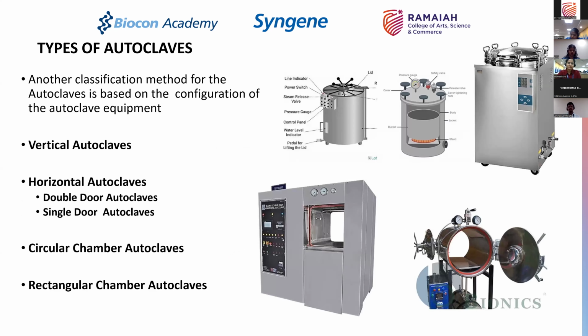Okay. Now, the third type of classification is also based on the geometry or the configuration of it. Now, when you look at the geometry or the configuration, what do I mean? There is vertical configuration which is something which looks like this. So in a vertical plane, there is always a water tank at the bottom where the electrical immersion heater is there. And then you have the bucket in which the equipment or the components which need to be sterilized is kept. And then you have a lid which has got a gasket and all the things with the safety valve, with the pressure valve, and with the temperature or pressure gauge, so that you can achieve this.